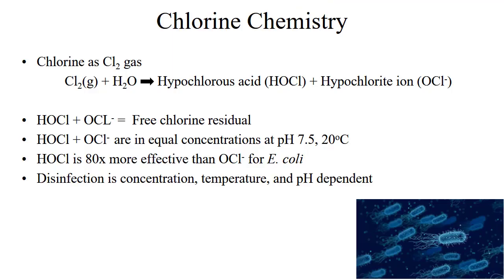There are several chemicals that can be used to inject chlorine into the water. One option is chlorine gas, which is Cl2. When chlorine is added to water, hypochlorous acid (HOCl) and hypochlorite ion (OCl-) are formed. The combination of hypochlorous acid and the hypochlorite ion is the free chlorine residual. This reaction is pH-dependent, and at a pH of 7.5, the concentration of hypochlorous acid and the hypochlorite ion are equal.